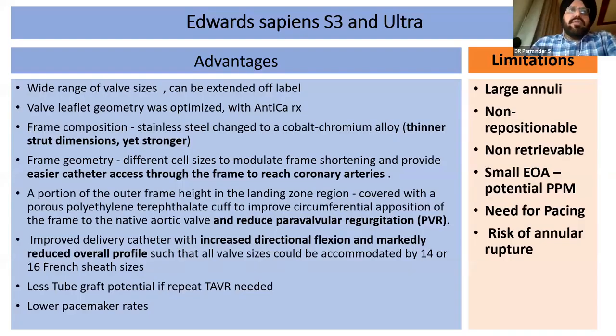So with Edwards, we have a wide range of advantages. We have a wide range of valve sizes, and even some people do extend it off label by adding some more saline or contrast to it. Valve leaflet geometry has been optimized. Frame composition has been improved. Frame geometry provides easy access to the coronaries. And the PET skirt provides protection against paravalvular leak. And there's an improved delivery catheter, which is 14 French or 16 French, which helps in reducing vascular complications. Further, there is less tube graft potential if repeat TAVI is needed. So balloon expandable valves are one of the favorite valves in case repeat TAVI is needed after degeneration of balloon expandable valves. We can easily go ahead with supra-annular valves. Further, they have lower pacemaker rates in comparison to self-expanding valves.